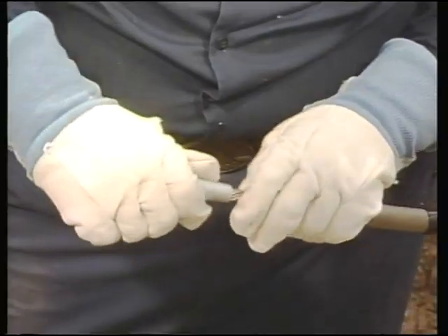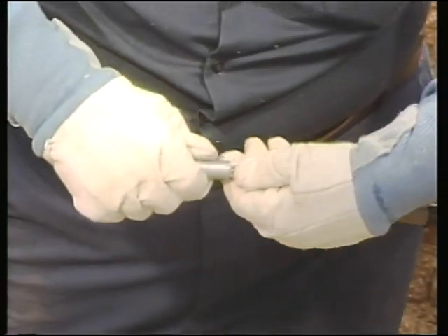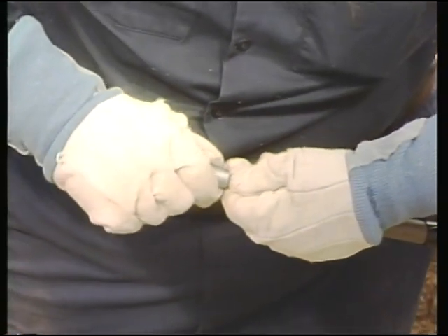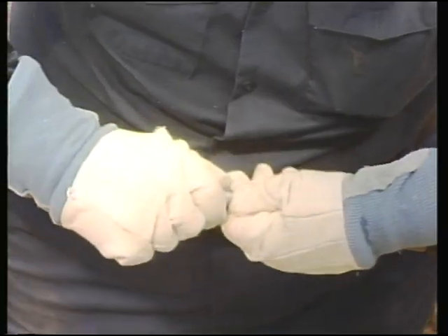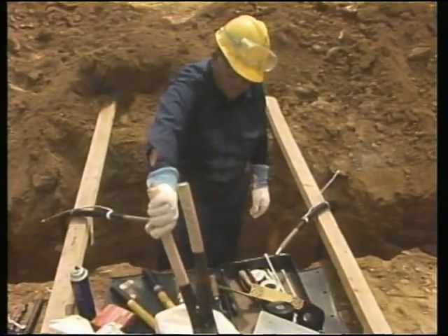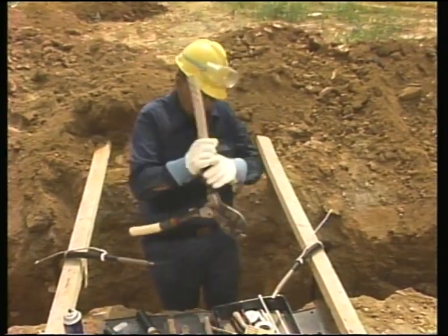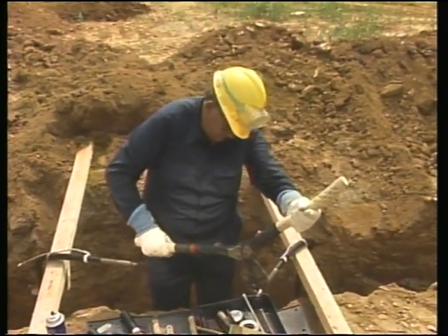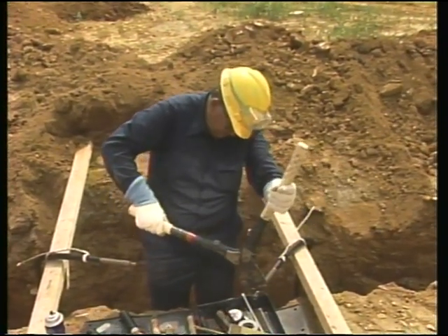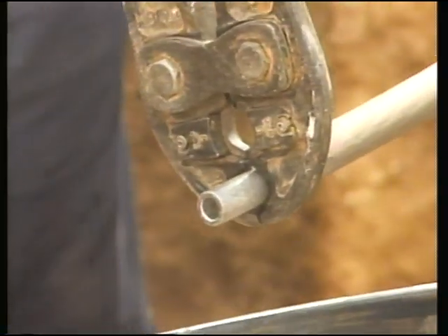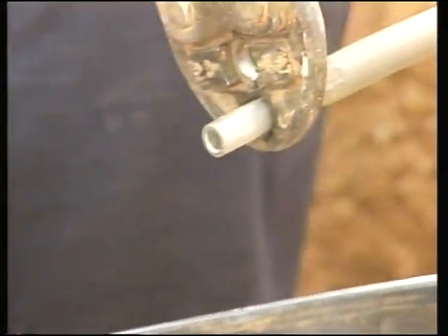The connector is then applied by placing it over the end of one conductor, making sure the conductor is fully inserted into the connector. Following the manufacturer's recommendations, the workman will apply the connector to the first cable end. He makes the required number of compressions in an outward direction from the middle of the connector.